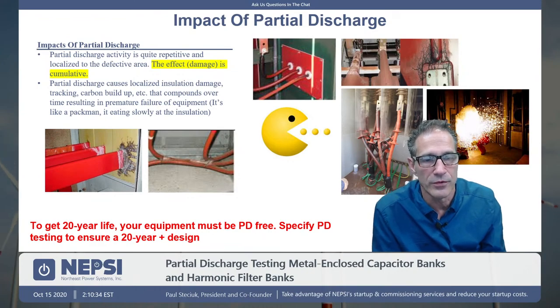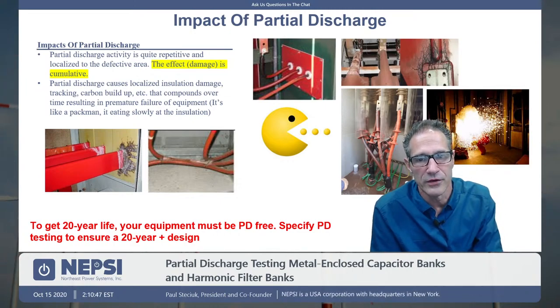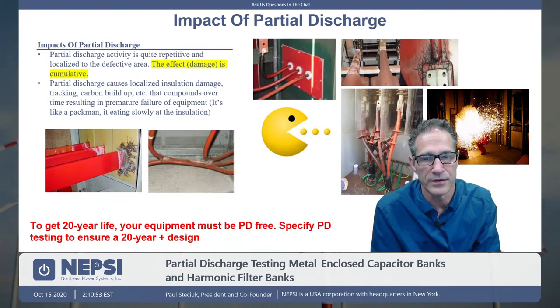It doesn't fail the equipment right away. It takes a lot of time for partial discharge to fail the equipment. But eventually it will fail the equipment. And it's a design defect to have partial discharge within your equipment. So if you're looking to guarantee 20-year life, you have to have partial discharge-free equipment. And that really comes down to the design.